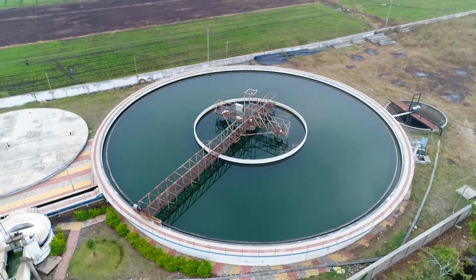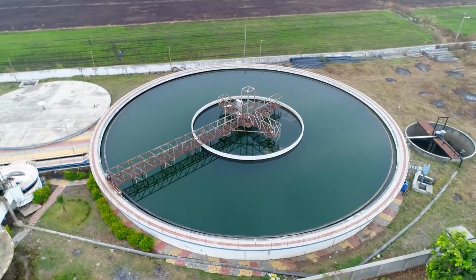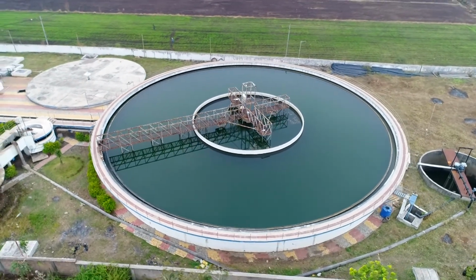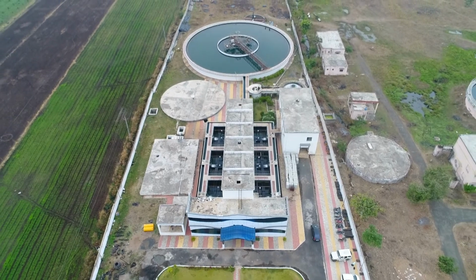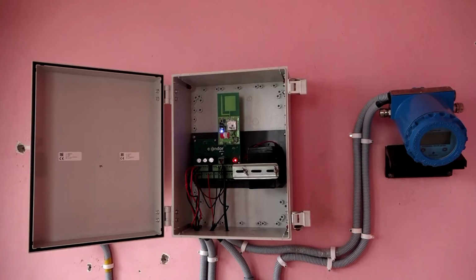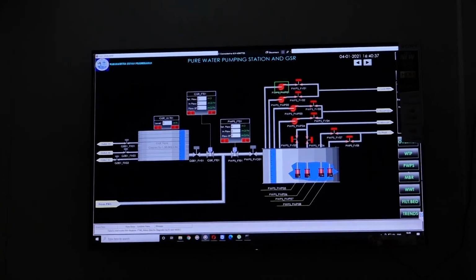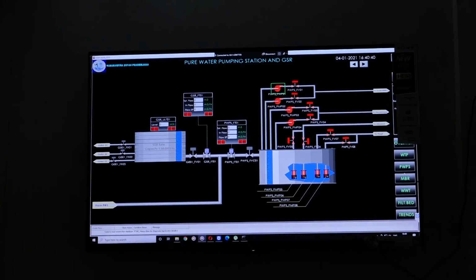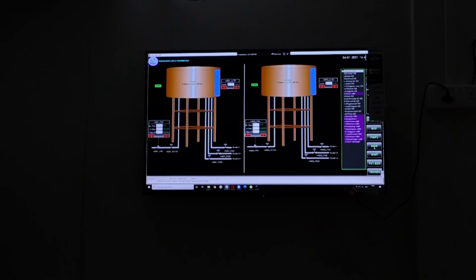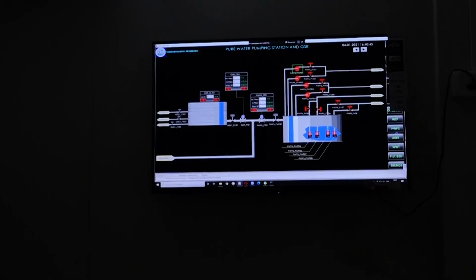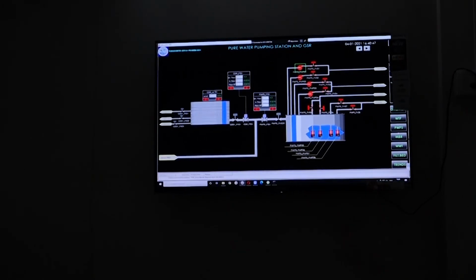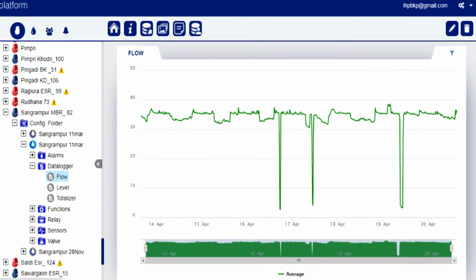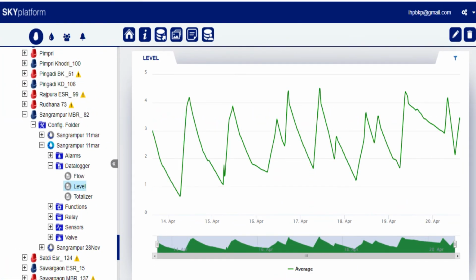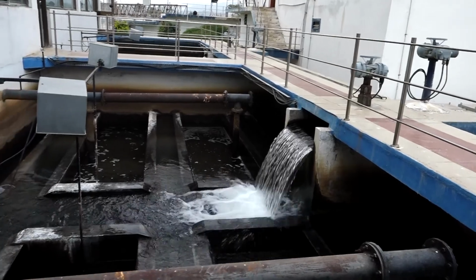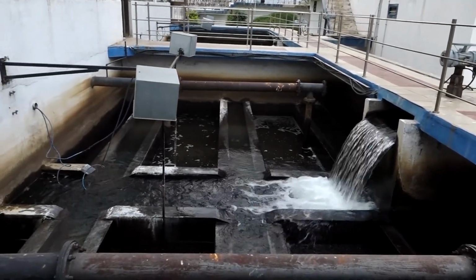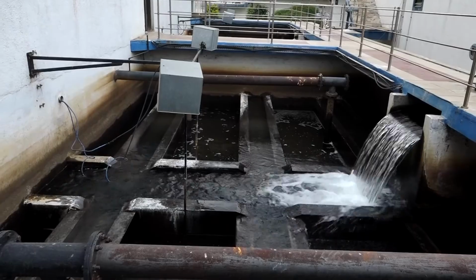A pure water sump of 9 lakh litres capacity was constructed at the WTP site. It has an ultrasonic level transmitter and an ultrasonic flow meter at the outlet of the sump, and it is interfaced with the PLC and controlled through SCADA. Once the MBR and GSR are filled, the water level in the pure water sump at the WTP goes down. An ultrasonic level transmitter senses the water level in the sump and gives the signal to the PLC for operation of the inlet valve at the water treatment plant.